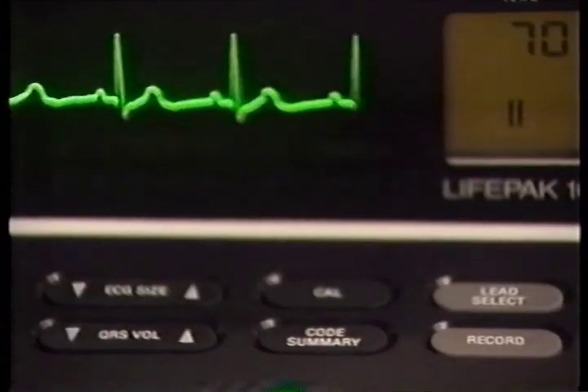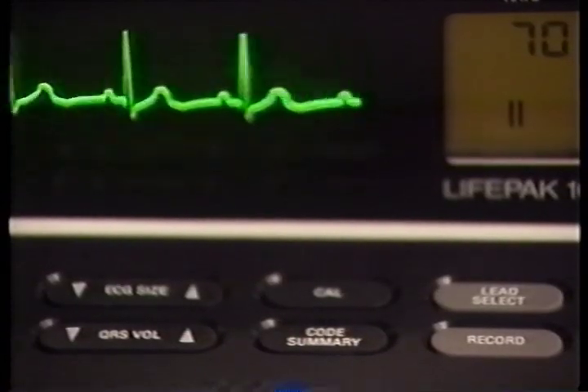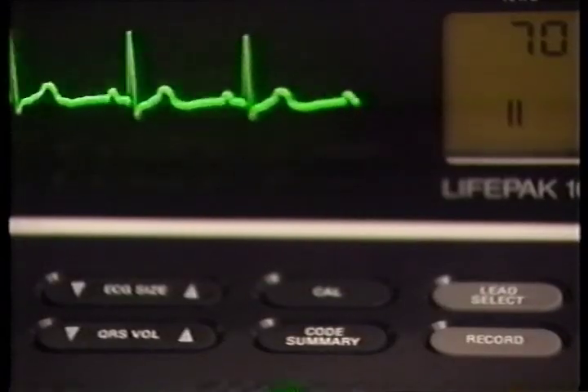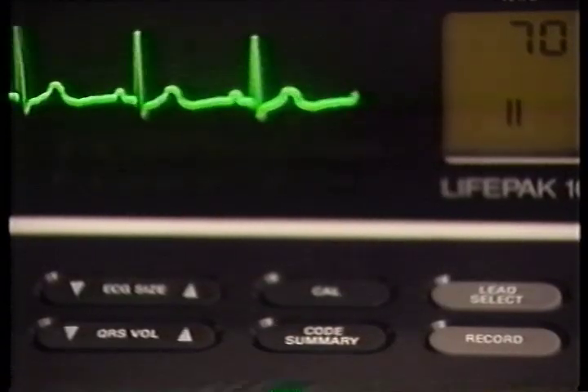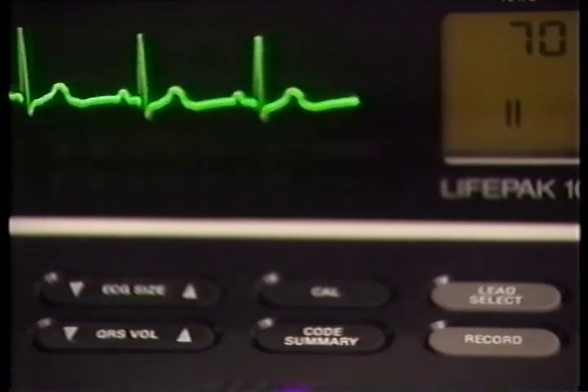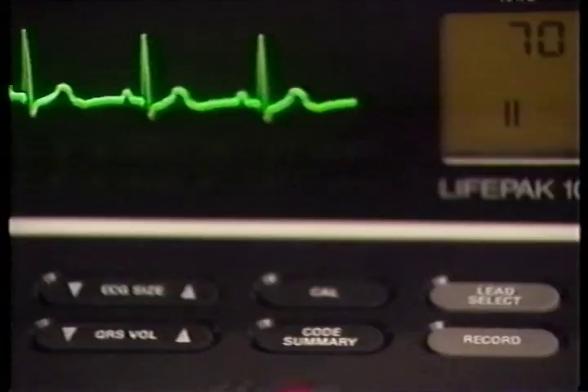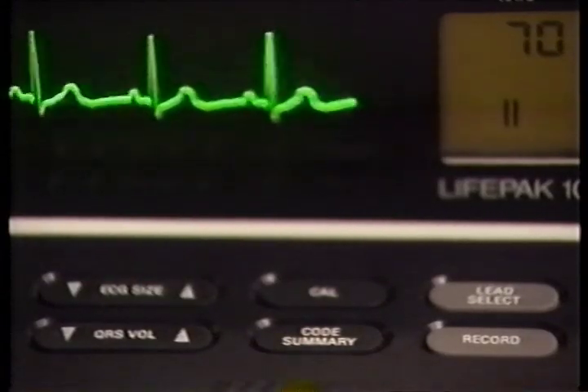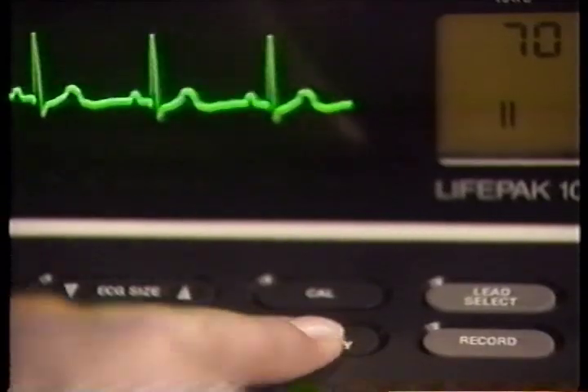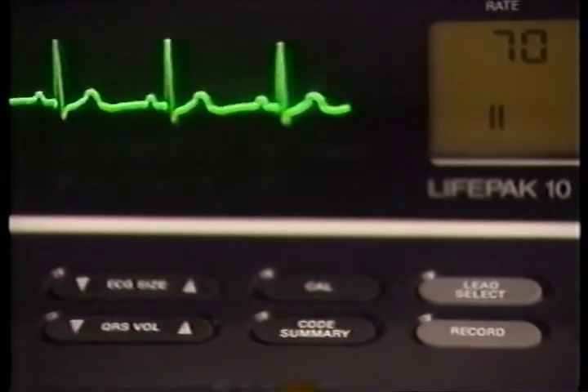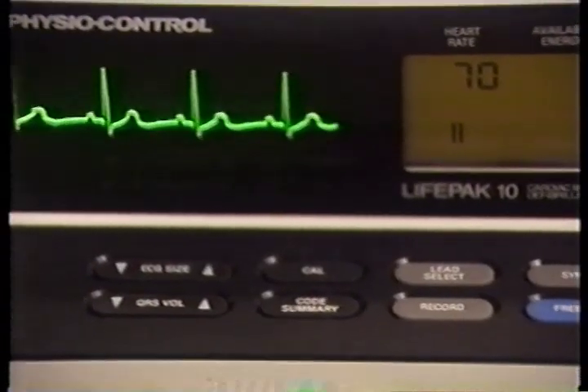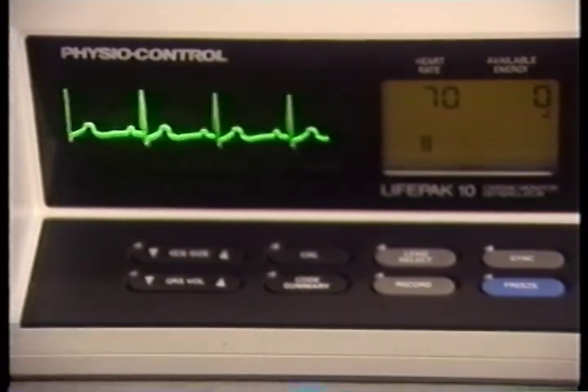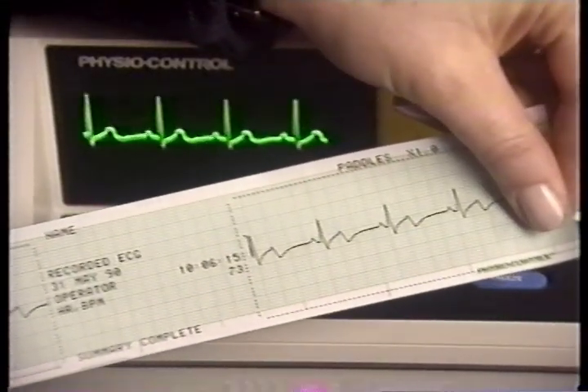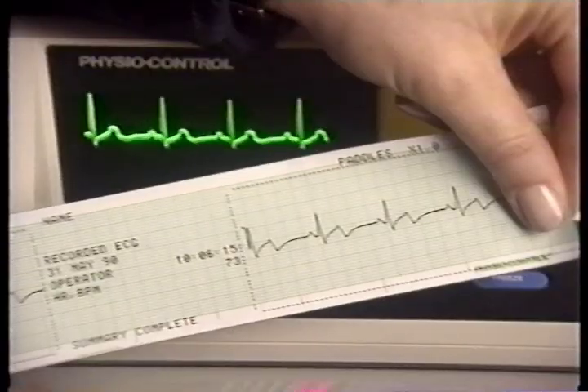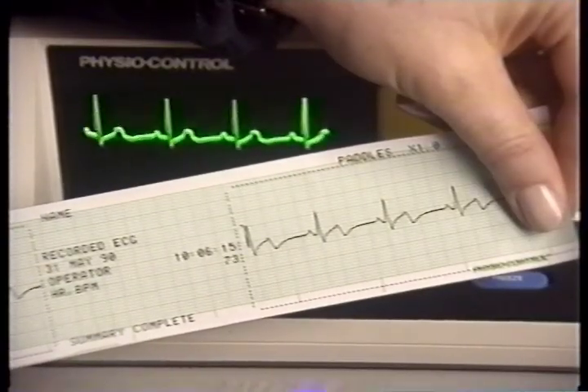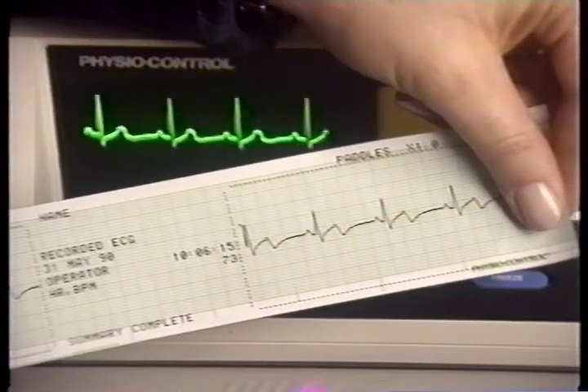The code summary critical event record allows documentation of ECG data during resuscitation and routine monitoring. The code summary memory stores approximately 20 critical events, including pre- and post-shock ECG data, user-initiated recordings, and pacemaker recordings. Once the LIFEPAK 10 is powered up, Code Summary begins storing critical information. Push the Code Summary button at any time to retrieve the stored data. It will retain data for 5 minutes after the LIFEPAK 10 has been turned off. To notify the user that all information has been printed, Summary Complete is annotated on the final segment. Printing the Code Summary report does not interfere with updating, nor does it clear the memory.